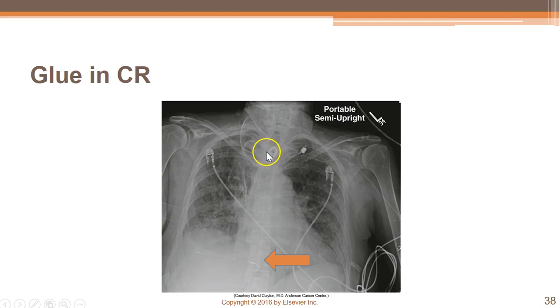And then I want you to notice this little thing right here. This is where they have had a tracheotomy, and so they have actually got a breathing tube in their trachea. So that's something else you could not remove. Those are types of artifacts that are there for a reason, and you don't have to worry about them, okay? But this down here is bad, especially if it showed up, you used it on 3 patients and it's in all 3 patients, then it has to be taken out of service because it affects your quality.